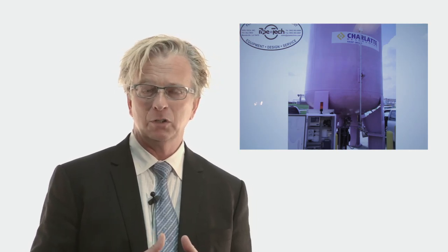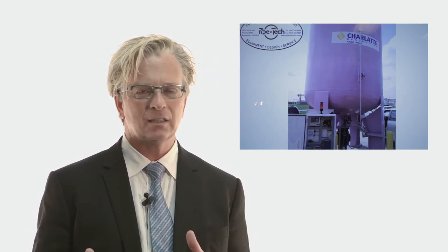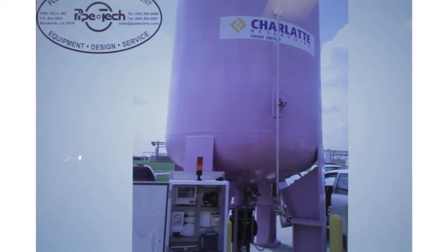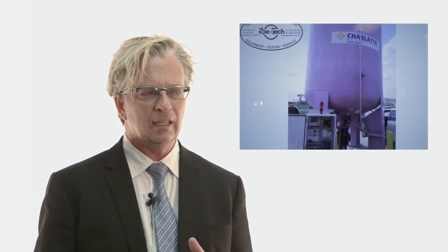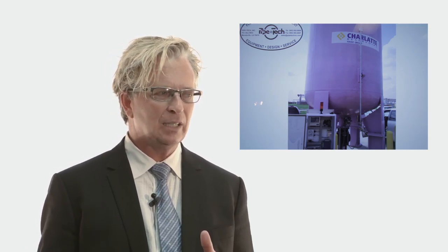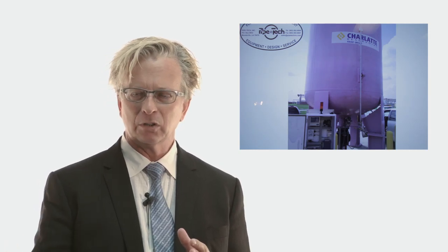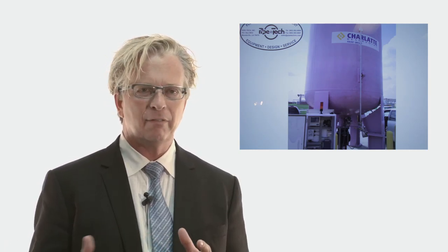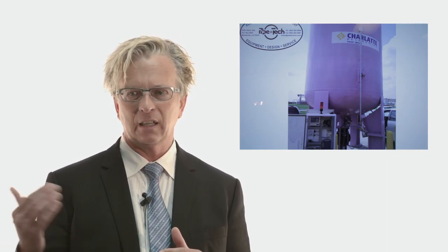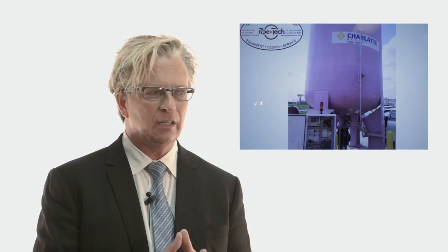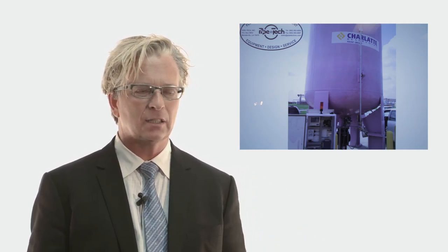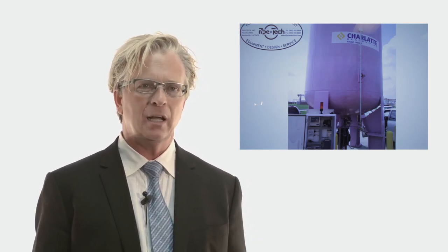The most important part of a reuse water system is the computer analysis and looking at the operation of the system. Here's an example of the surge vessel, and in the bottom left-hand corner you'll see the transient monitoring computer. It records data — we look at this once a year to make sure of normal operation. It records day-to-day operation of the pumps and pressure at a given time step. It will also record transients that occur, and if a transient does occur coming from a source like a control valve, it'll read and record that transient and send an alarm back into the SCADA system so that operators know we've had an upset in the piping system.